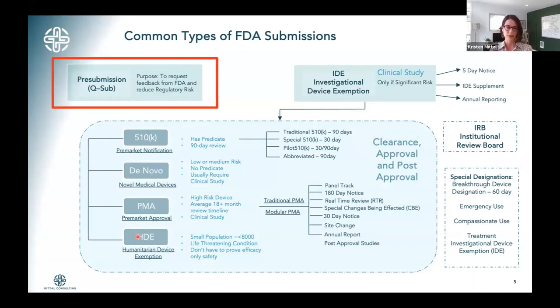So in this case, you can do a humanitarian device exemption, which is similar to a PMA, but you only have to prove safety — you don't have to prove efficacy. So the burden of proof is slightly lower so that we can at least get more technologies like this on the market.